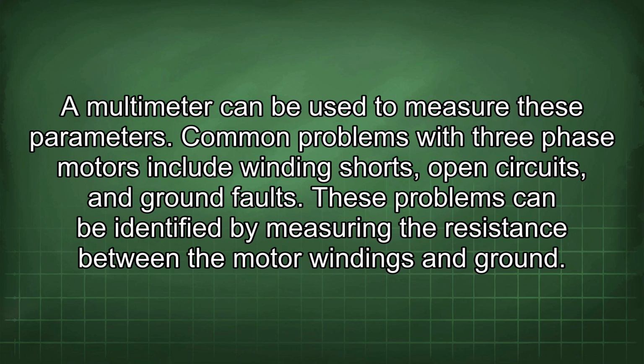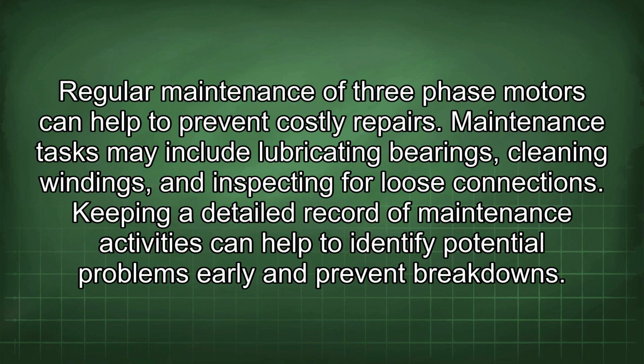Common problems with three-phase motors include winding shorts, open circuits, and ground faults. These problems can be identified by measuring the resistance between the motor windings and ground. Regular maintenance of three-phase motors can help to prevent costly repairs. Maintenance tasks may include lubricating bearings, cleaning windings, and inspecting for loose connections. Keeping a detailed record of maintenance activities can help to identify potential problems early and prevent breakdowns.